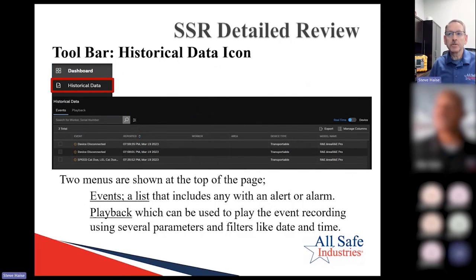Next is the historical data menu of the toolbar. When you click on it, you'll see two primary menus on this page: events and playback. Events are not every line of data coming out of the sensors—that's just when an instrument has an event, whether an alert or an alarm. So again, it's highlighting the most important stuff as you're out doing your wireless gas detection. This is a list of events for any alert or alarm on any of the instruments you have connected.